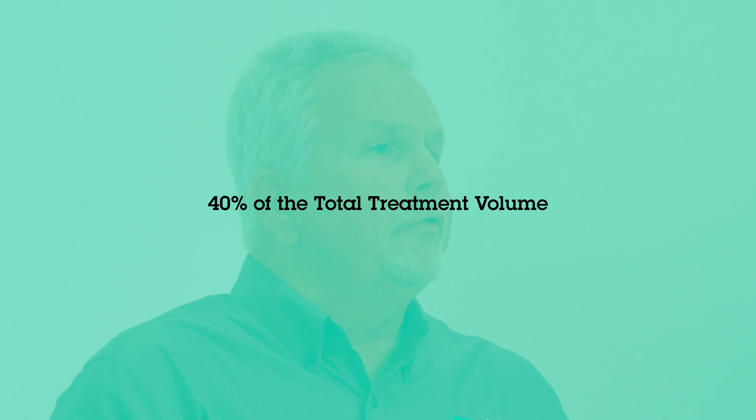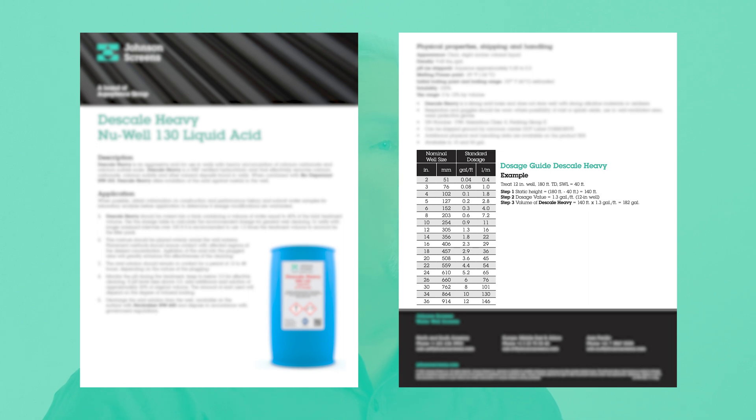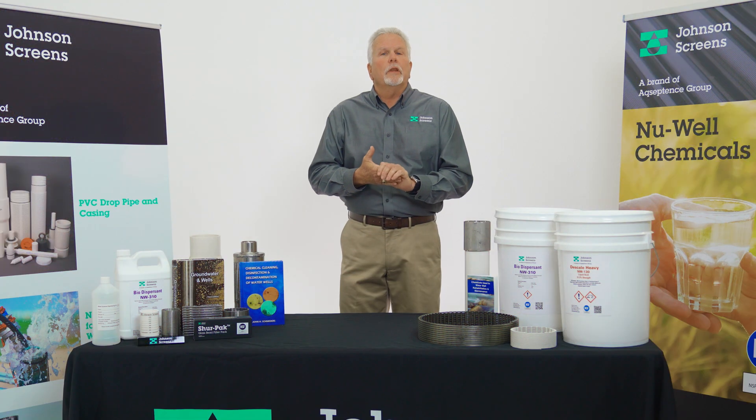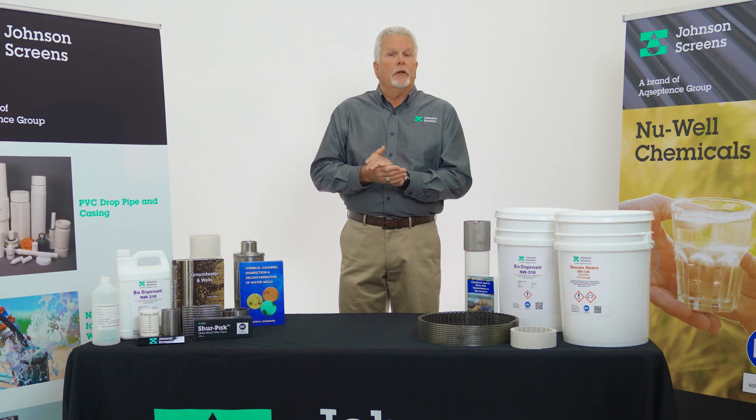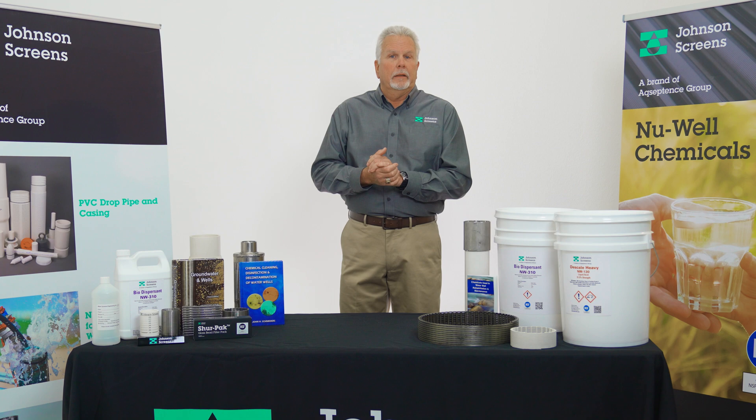Step 1. Descale Heavy Nu-Well 130 should be mixed into a tank on the surface containing a volume of water equal to 40% of the total treatment volume. Use the dosage tables to calculate the recommended dosage for a general well cleaning. In wells with longer screen intervals — over say 100 feet — it's recommended to use one and a half times the treatment volume to account for the filter pack and well formation.